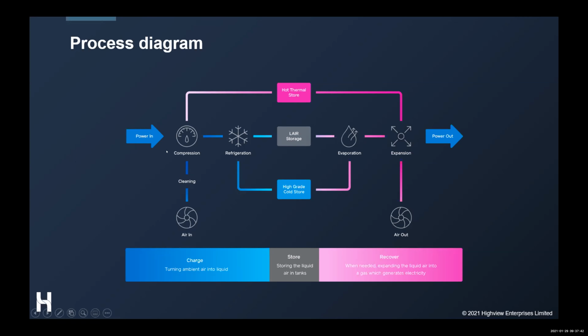So when we've compressed our gas to 60 bar and we've removed the thermal energy from it, we put it across our liquefaction system, or what we have here denoted as refrigeration. We have a cold box, which comprises a number of cryogenic process equipment, and we cool the gas down in what we call a main heat exchanger, which is a brazed aluminium plate heat exchanger. We cool the gas down from about 20 degrees down to minus 150 degrees Celsius. And then we throttle it across a Joule-Thomson valve, which is a valve with a very large pressure drop, a very large restriction. And the gas goes from being supercritical pressure to subcritical pressure and drops into the saturation dome. It turns into a two-phase fluid, I should say. And the liquid is drawn off in a separation vessel and pumped into our liquid storage system.